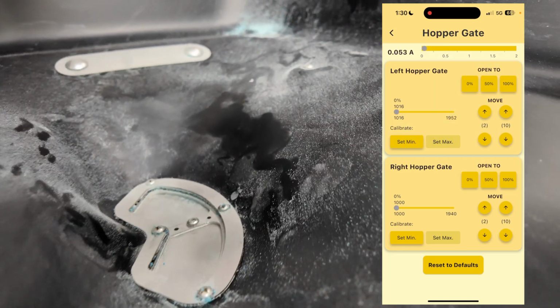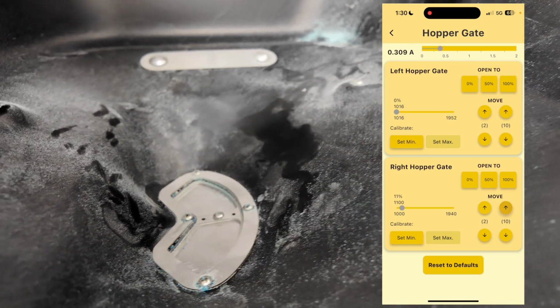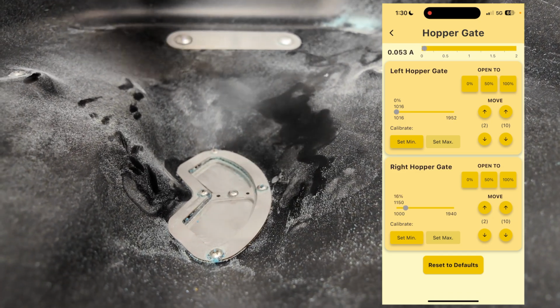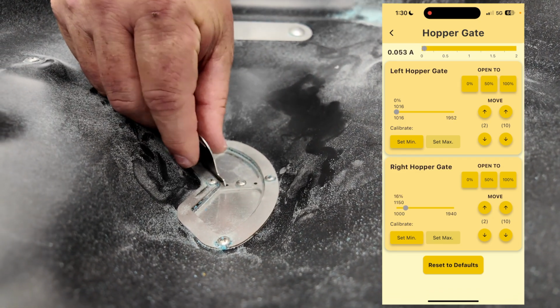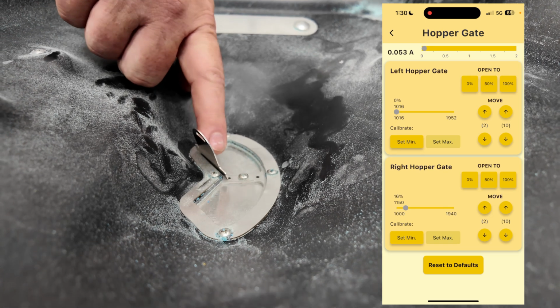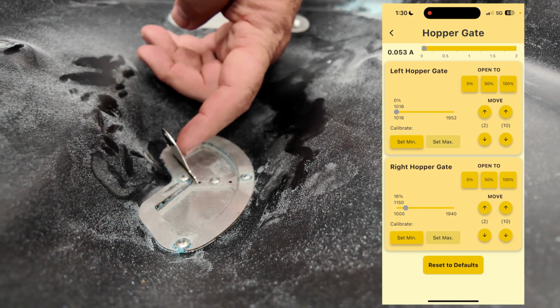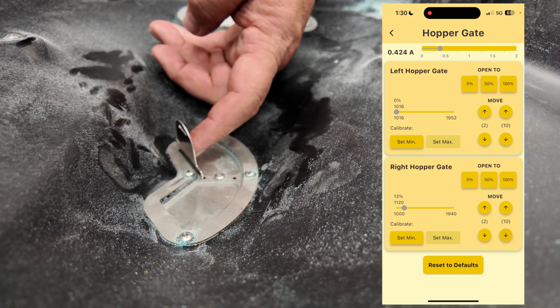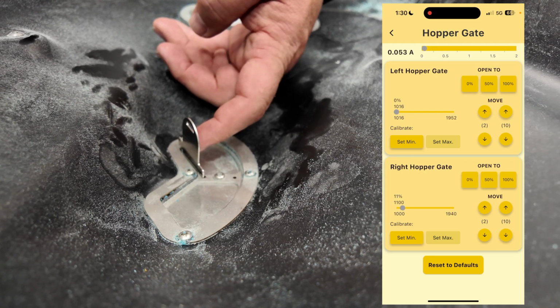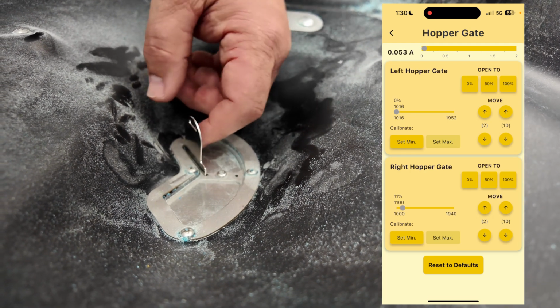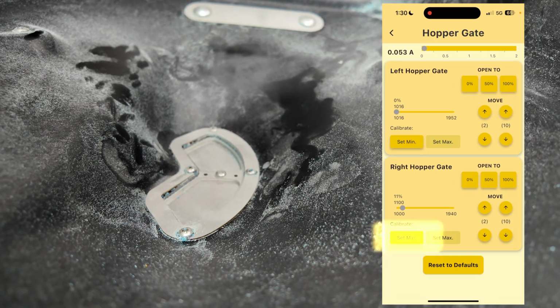I'll go to the other side and start opening it up by hitting +10. I'll put my calibration key in and press very slightly forward, then I might go ahead and hit -10. You can see it moving, and there - straight up and down. So that's set properly. I'll hit set min.